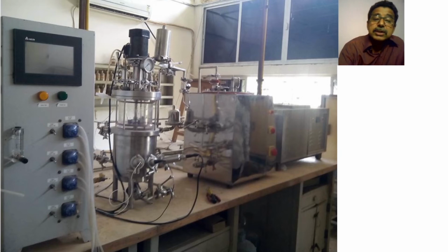Okay, one more probe is the dissolved oxygen probe, the PO2 probe. This detects the dissolved oxygen inside. That is also controlled automatically. So when the dissolved oxygen level drops down a little bit, then the agitation speed increases or aeration increases. Here on the control panel, on the right side, you will find blue colored peristaltic pumps 1, 2, 3, 4, where I say one is acid, one is alkali, and the third one is anti-foam.